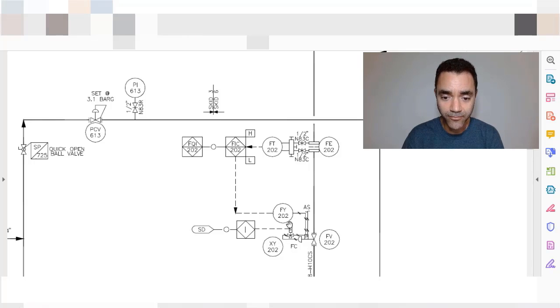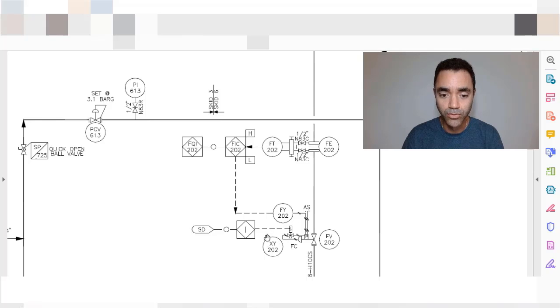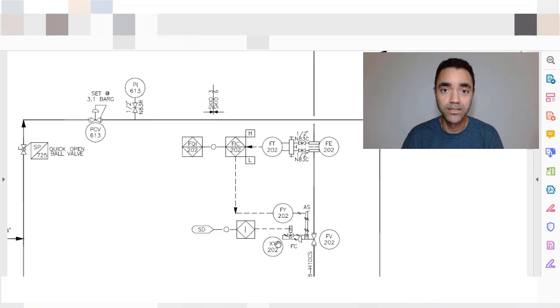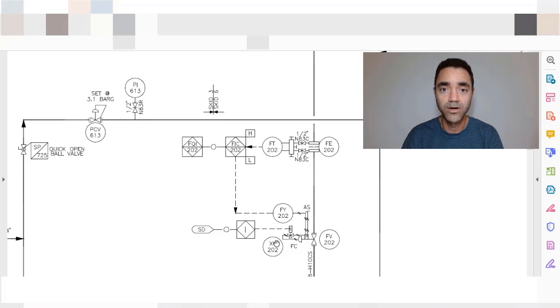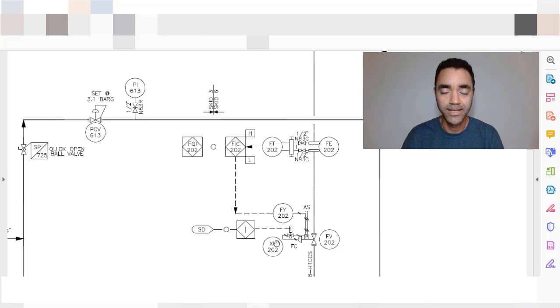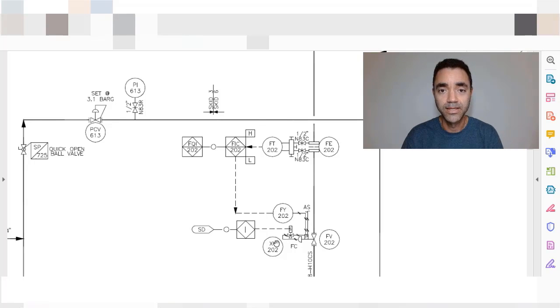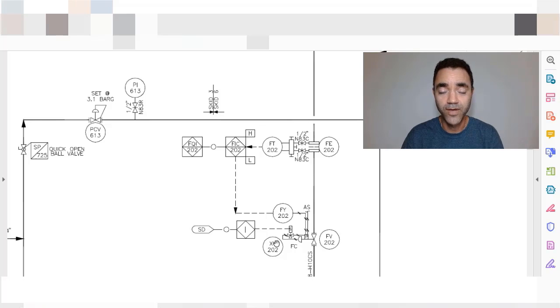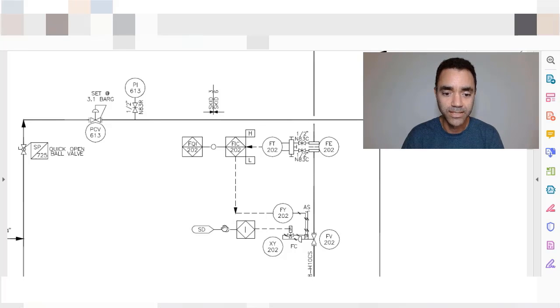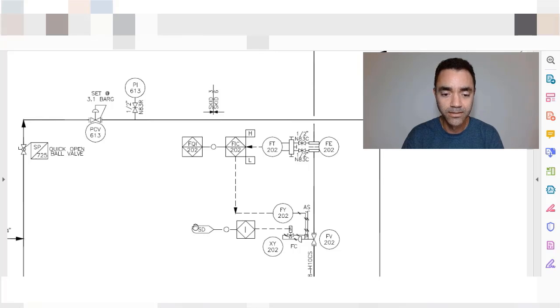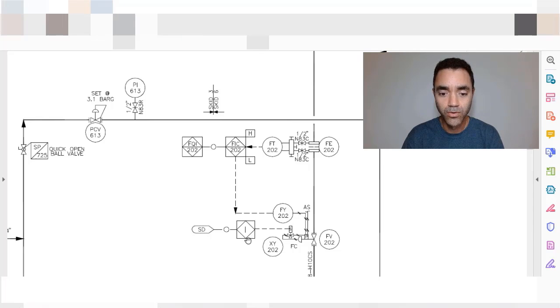We have here a solenoid to actuate faster the valve in a case of incident, accident, or something that is important to the fast shutdown of the valve. That's why we have the SD here as a signal going to I that represents a safety interlock.